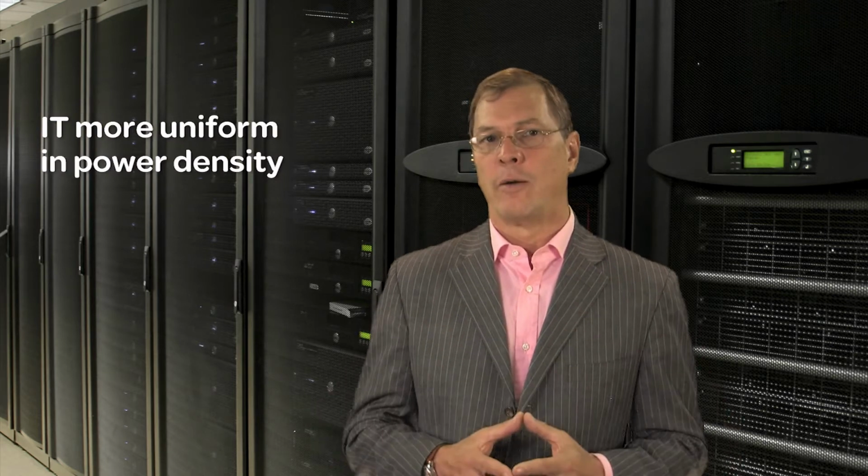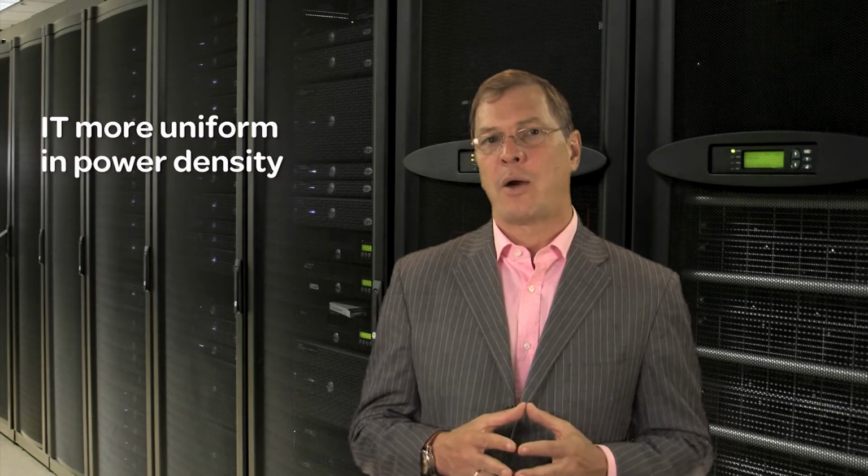Well, cloud computing has some very interesting impacts on the technical attributes of data centers. There's four key areas where we feel cloud is changing the data center design of today. One is the IT equipment itself used in cloud designs tends to be more uniform, and particularly uniform in its power density. And because of that, it allows us some flexibilities in designing the data center and opportunities to optimize better around a single density rather than around a variable density, which gives us the ability, perhaps, for example, to increase the efficiency of the data center.